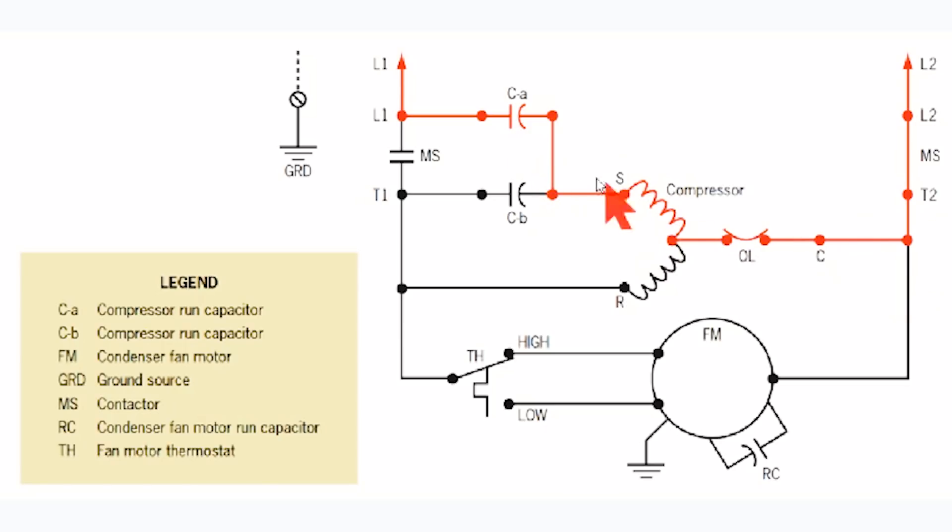So it's charging and discharging, charging and discharging. What happens is when this switch is open, when the compressor contactor contacts are open, you have a constant path. So even when this compressor goes off, there's still a small amount of current dictated by the size of this capacitor that moves in and out of this compressor.